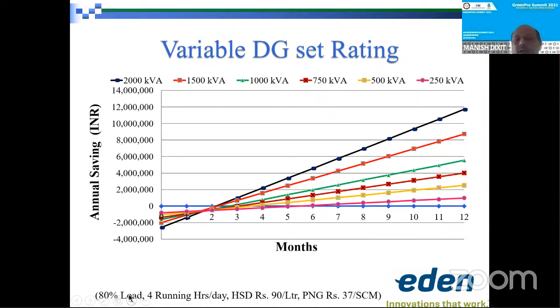This is considering 90 rupees per liter of diesel and 37 rupees per SCM of gas. In some parts of India, the SCM of gas is around 32 or 28, and diesel cost has now increased to 95 also. This is based on 4 hours running per day at 80% engine load, so when the load varies, the saving would also vary, but this gives just an idea. I'll show you how it changes with different loads.